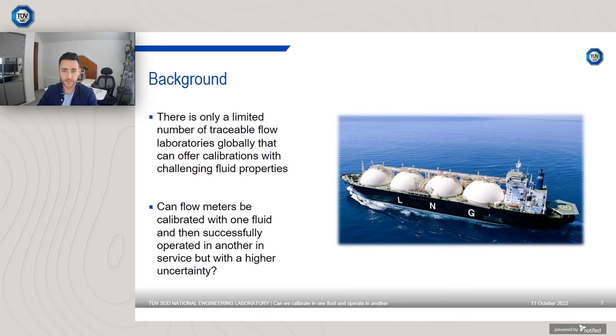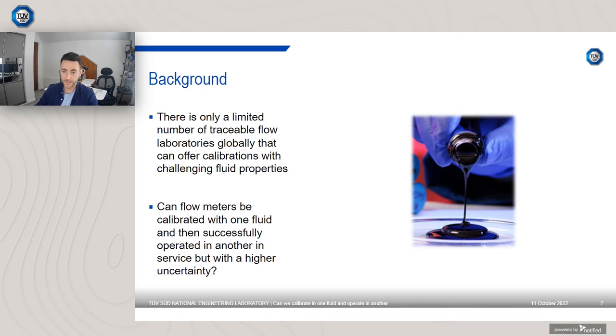There's a lot of different LNG cargo ships. It currently is measured. However, there's a lack again of traceable accredited laboratories. There is one in the VSL facility in the Netherlands, a facility for the calibration of LNG flow meters, but there's not a lot. A lot of the work they're looking at just now is whether you do need a substantial large LNG calibration laboratory, or can certain meters be calibrated in a different fluid as well. So there is that calibration transferability that's been explored as well as part of their facility.